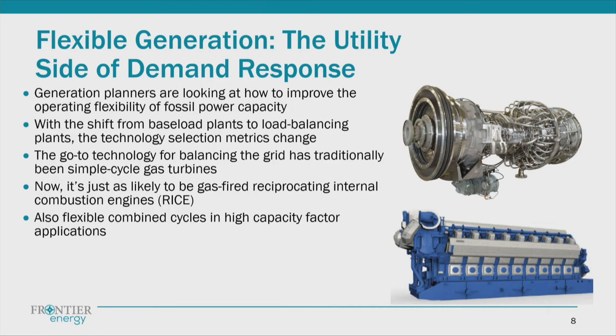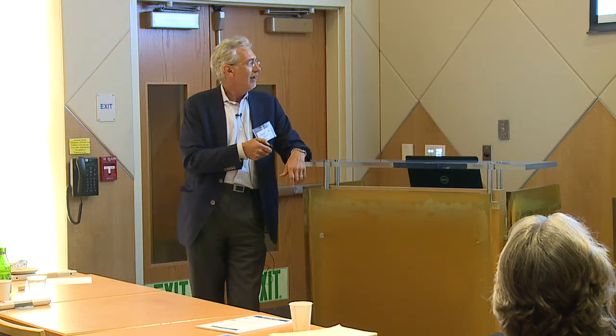In the gas turbine world, combined cycle power plants use very large turbines they call heavy frame turbines. But these are kind of an adaptation from the peakers, as they are called, aeroderivatives. They literally are derived from jet engines. And so they have good efficiency, they fast start, they ramp, they do all these things. But sometimes full throttle isn't enough. So you build a hall with 10 to 12 engines.